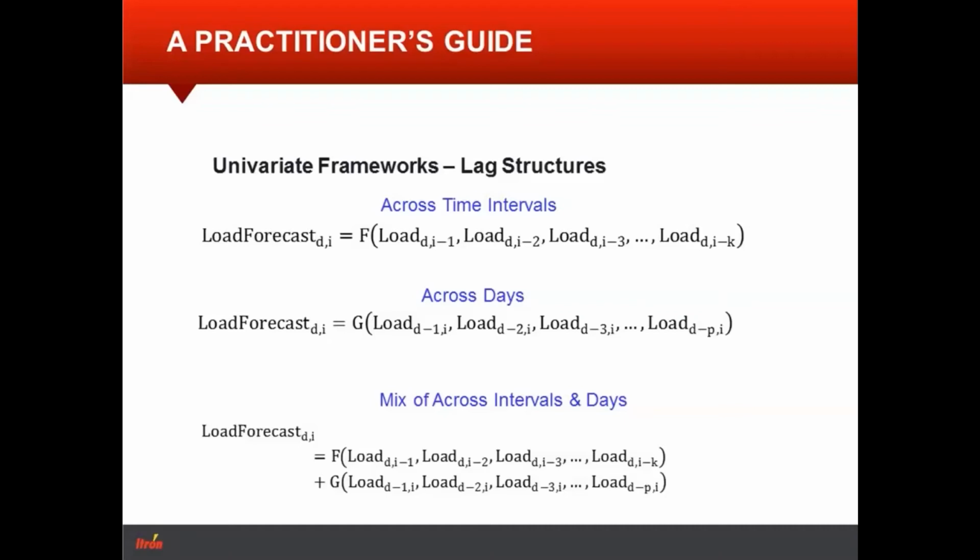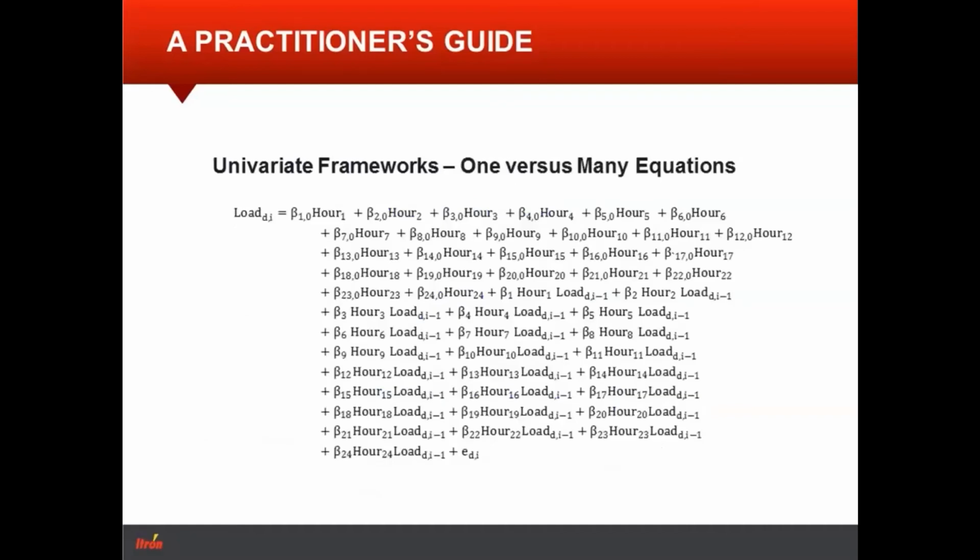It also depends on what your forecast horizon is. So for example, if I'm forecasting 1 hour ahead, knowing what loads were that prior hour is very powerful. But if I'm forecasting 10 years from now, knowing what happened at 11 a.m. is not going to be very powerful. So you have to put in context what the forecast horizon is and how far that horizon is relative to the last bit of real information that you have available to you. So that's all discussed.